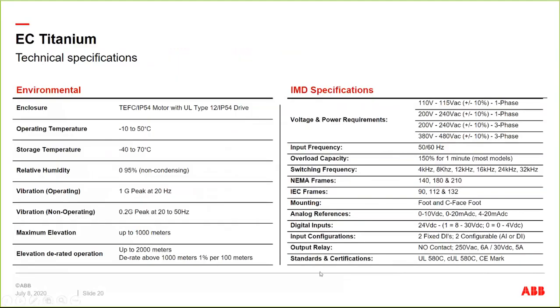And then this is the specification. On the integrated units, you have the full voltage tolerance associated with the standard drive. From a thermal standpoint, when you have an integrated drive, it's an electronic component. Think about your cell phone. You take it out into minus 10 degrees Celsius weather, it's not going to operate. Well, a drive is no different. It has a low temperature range and a high temperature range limit. So it's minus 10 to 40 degrees C, and then you derate per degree C up to 50 degrees C maximum. And it is fully IP54 as standard.